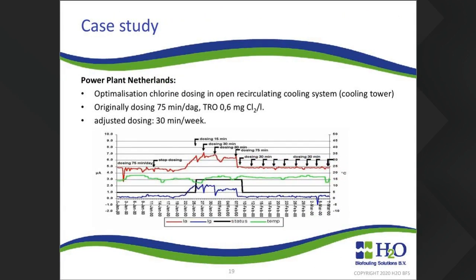Now, we applied this system at different locations, and this is an example of a graph we created at the power plant in the Netherlands with an open recirculating cooling system. So we measured in the cooling tower basin. Originally the plant applied a 75-minute dosing per day with hypochlorite with a level of 0.6 milligram per liter total residual oxidant. By using this probe, we got a signal of biofilm buildup.